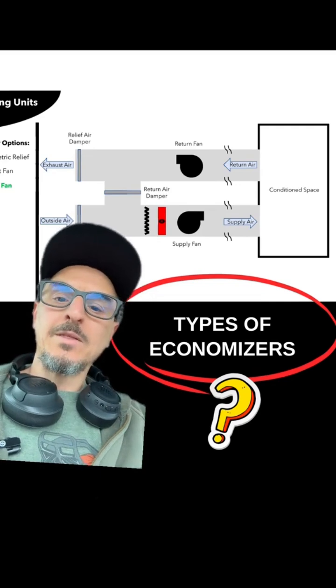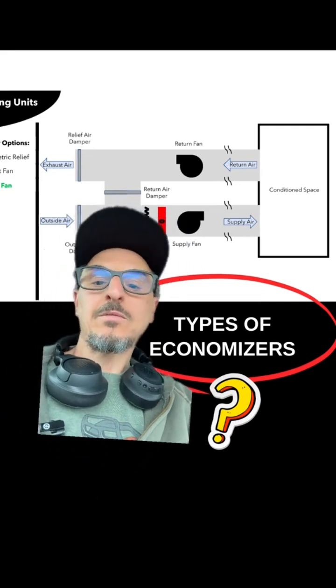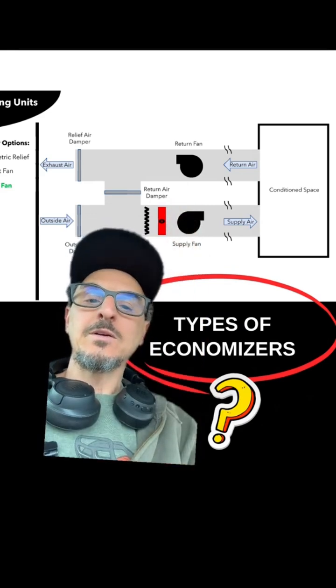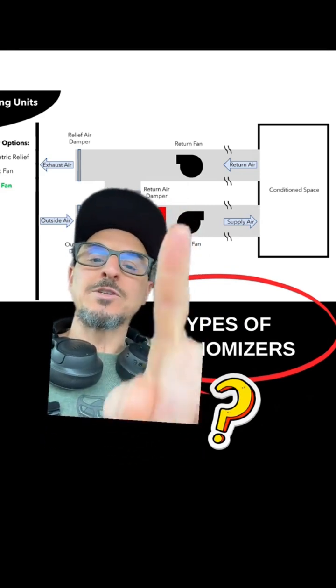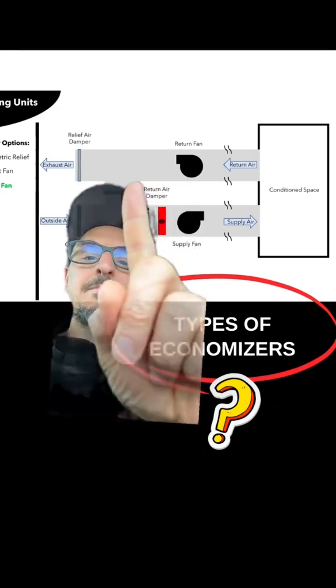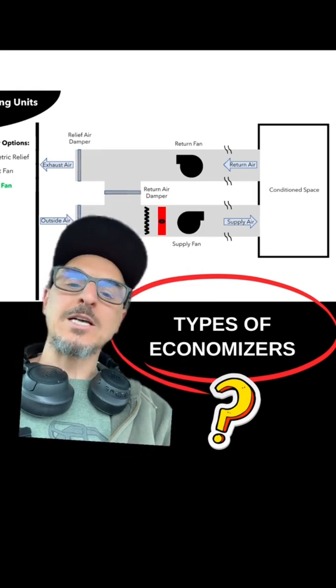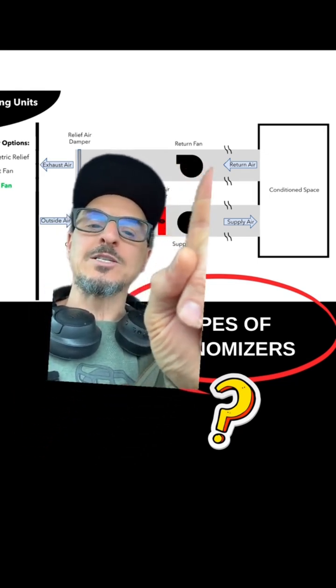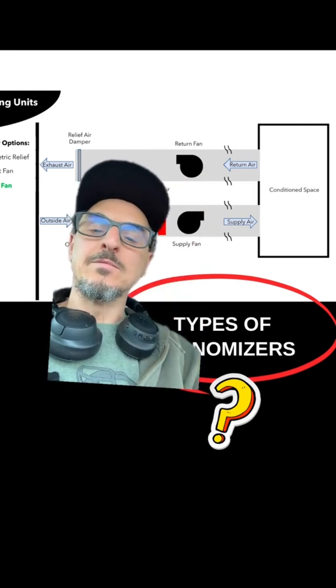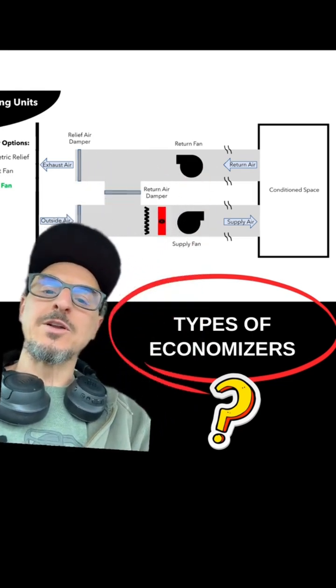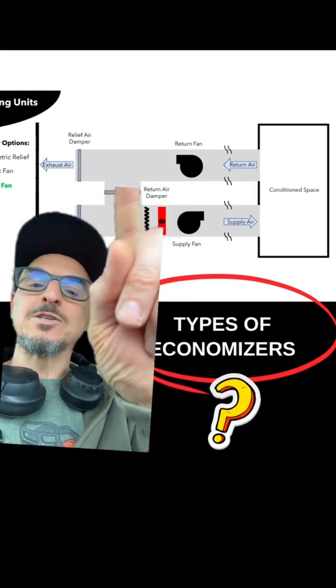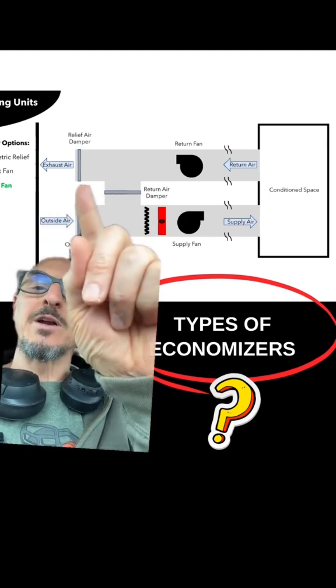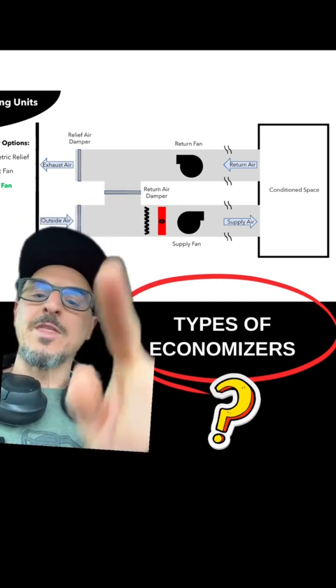The least known but best one for control is called a return fan economizer. You have a return fan here, and this works very well with large hospitals or multi-story buildings because this fan is responsible for making up all the pressure drop in the return duct. It pressurizes the plenum, and then you simply modulate the dampers — whether you want to release some, return some — and you have your outside air damper here.